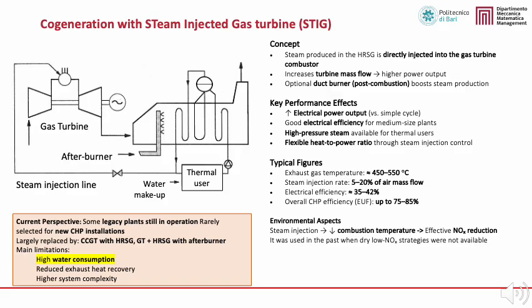This slide summarizes cogeneration systems based on the steam injected gas turbine or STIG cycle. First, regarding the operating principle, steam produced in the heat recovery steam generator is partly directed to the thermal user, while when there is no request for heat, steam is directly injected into the gas turbine combustor. This increases the mass flow through the turbine and therefore raises the electrical power output. When required, a duct burner or post-combustion system can be added downstream to further increase steam production for thermal users.